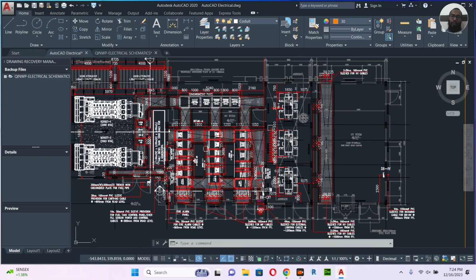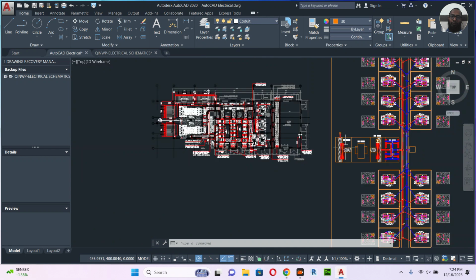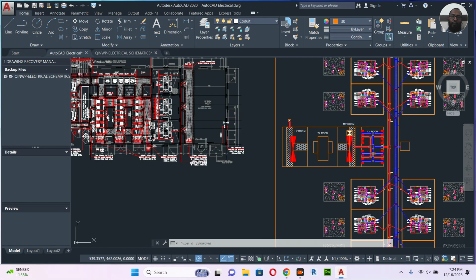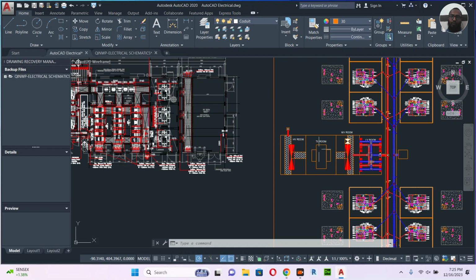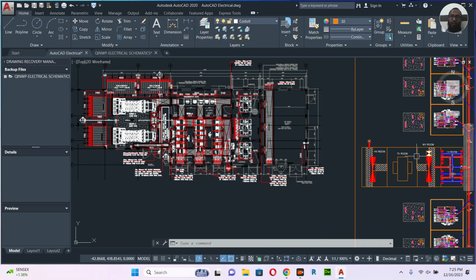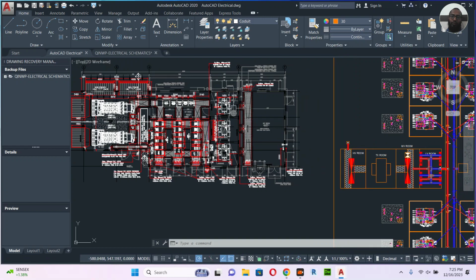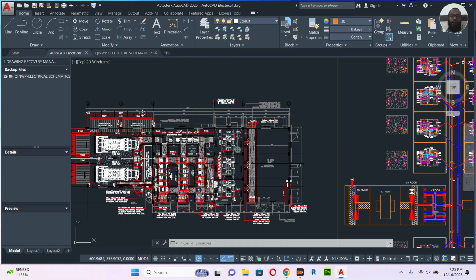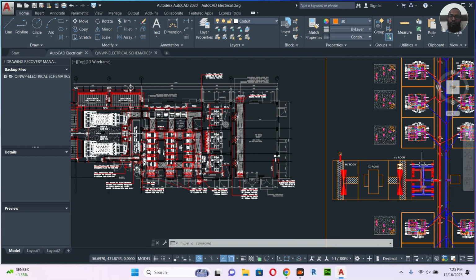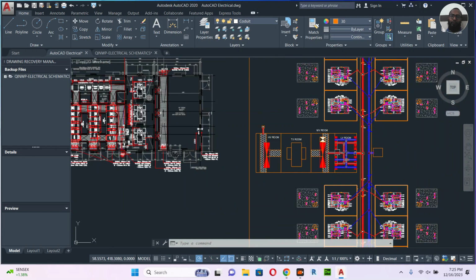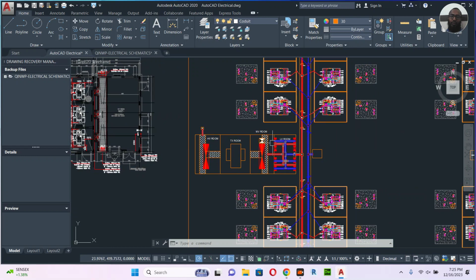So if you see, this is one kind of substation room with many things. Actually here we have 3 transformers. So this is the HV room, same like the HV room here, and then the transformer room, same like the transformer room. Then the MV room, what is here is the MV room, and there is no LV room here because this one will provide the power supply direct to the building. So in the individual electrical rooms there are some SMDBs. We have provided one LV room here because I don't want to provide anything outside.